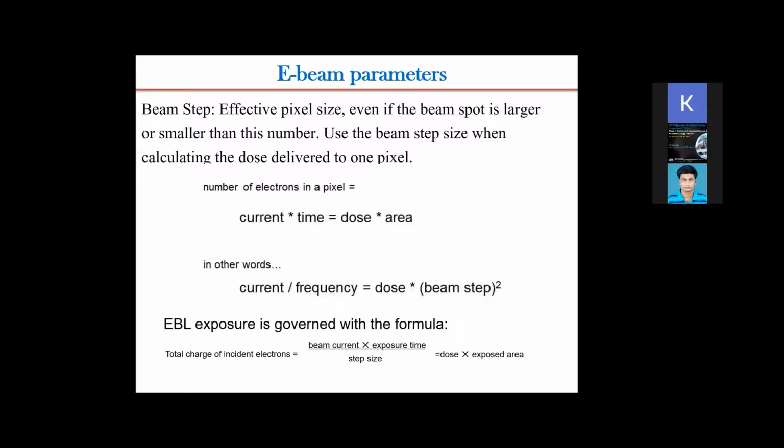So another parameter that you can play is the beam step. Effectively the pixel size, you can say, will govern the beam step. There is a formula you can choose for the beam step, but use the beam step when calculating the dose that has to be delivered to 1 pixel.